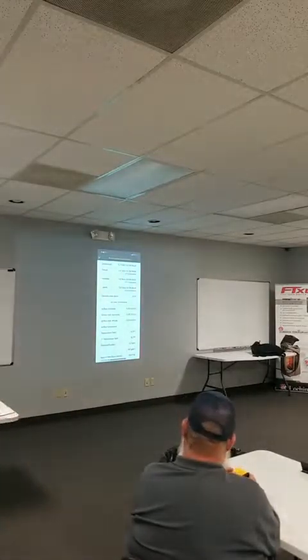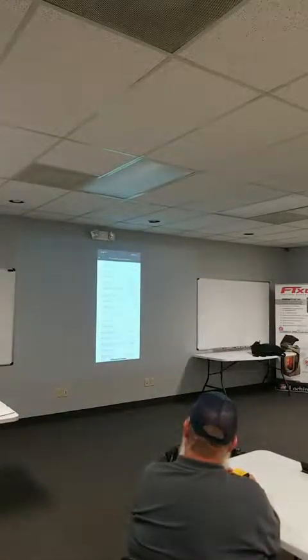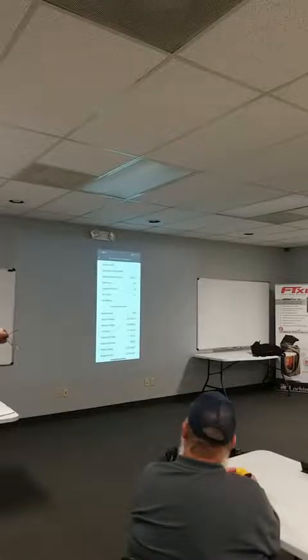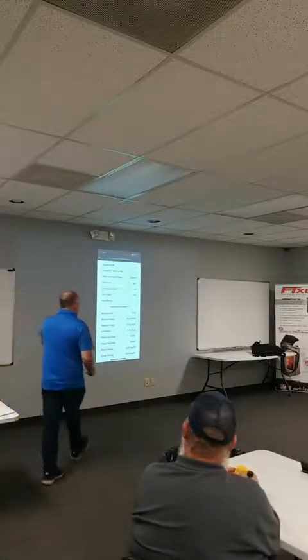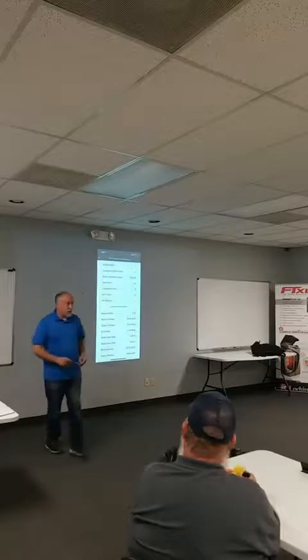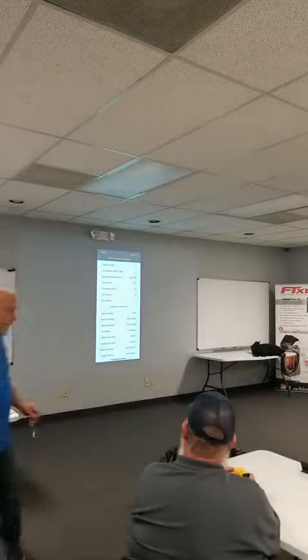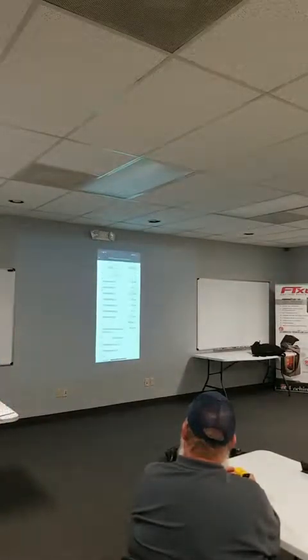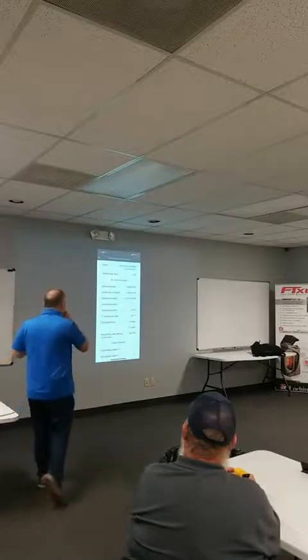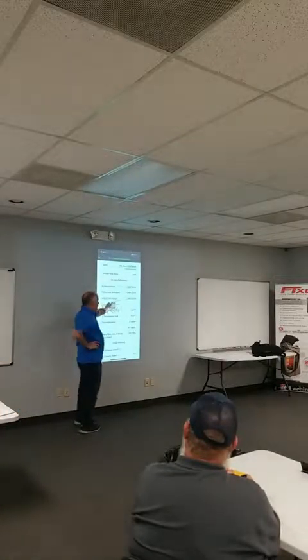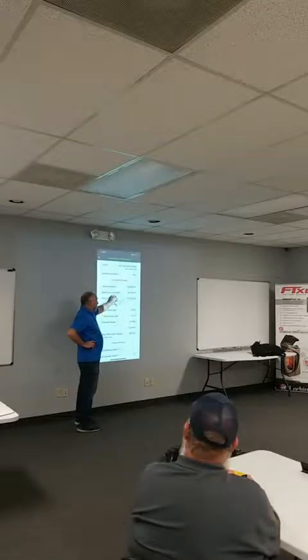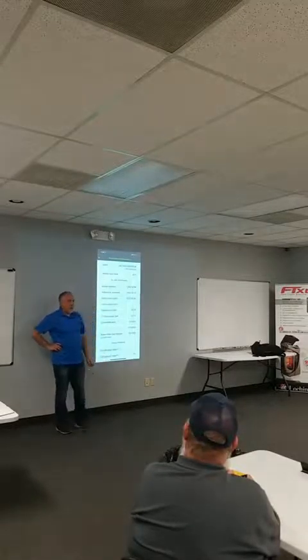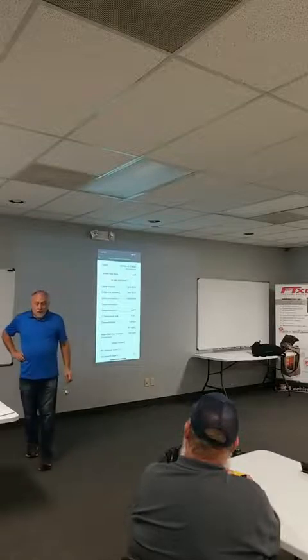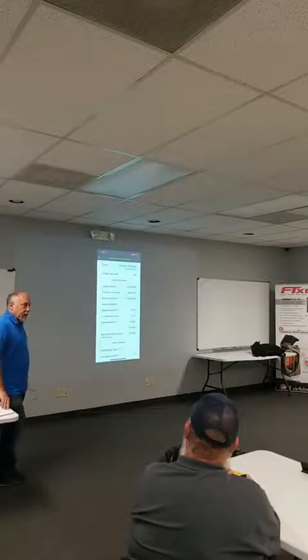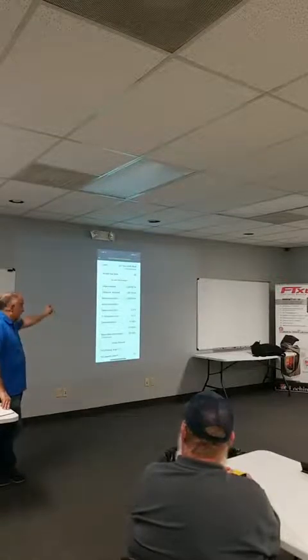Measurequick is actually calculating down here so the return air density is not 0.075, it's 0.072. Right, so I took 0.072 actual CFM. What it means is we're moving 1,560 actual CFM to get an equivalent of 1,400 standard CFM of air. So when you're setting up equipment and it's really hot and humid, you got to make sure you have enough standard CFM, not just the actual CFM.